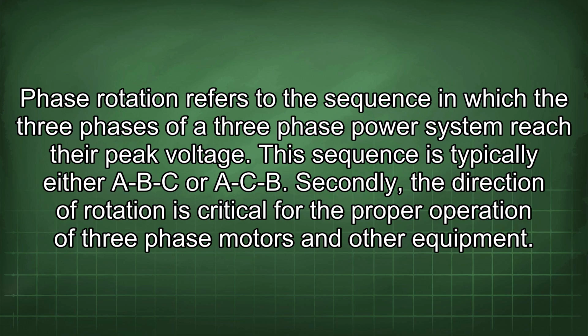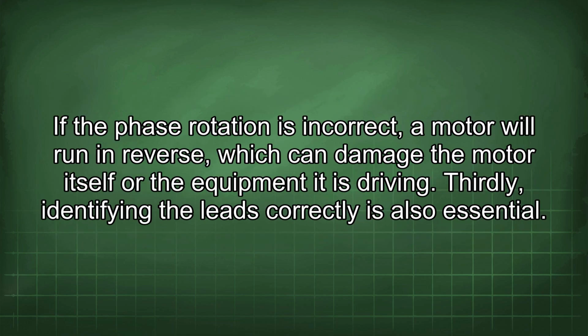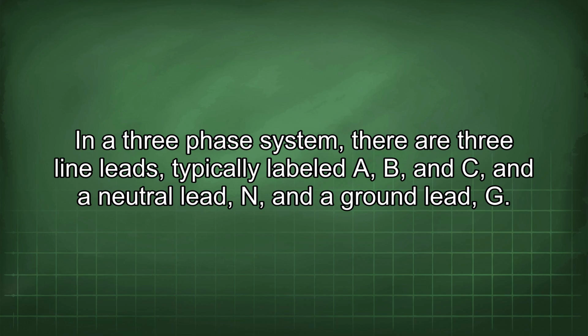Secondly, the direction of rotation is critical for the proper operation of three-phase motors and other equipment. If the phase rotation is incorrect, a motor will run in reverse, which can damage the motor itself or the equipment it is driving. Thirdly, identifying the leads correctly is also essential. In a three-phase system, there are three line leads typically labeled A, B, and C, and a neutral lead N and a ground lead G.